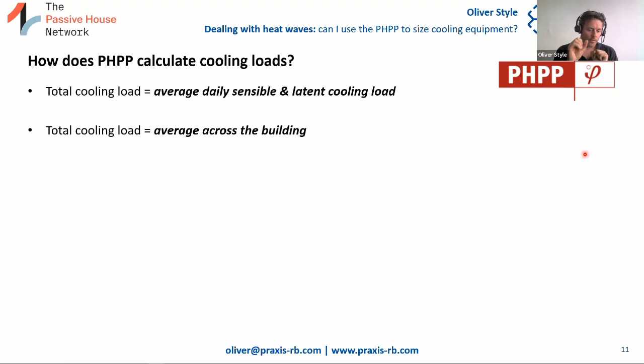But it's important to understand that an average across a building might not reveal differences in specific zones. Okay, and the boundary conditions, at least for small residential buildings, when the PHPP calculates the cooling load, is it takes the average daily outdoor air temperature, dew point, and solar radiation data. So again, that's a 24-hour average. The peak will be a lot higher than that. And it might be that peak that gives you 6 hours of really real discomfort in the building, in which the cooling equipment needs to be able to get that heat out of the building.